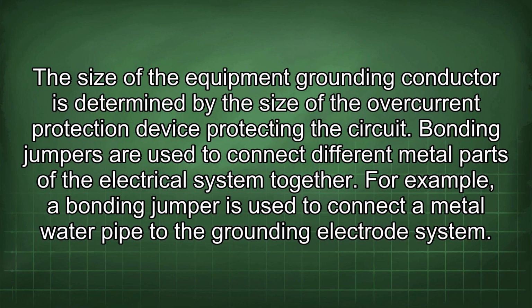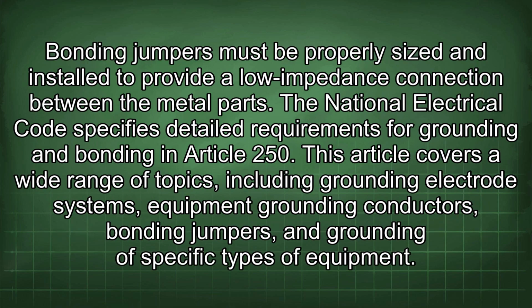Bonding jumpers are used to connect different metal parts of the electrical system together. For example, a bonding jumper is used to connect a metal water pipe to the grounding electrode system. Bonding jumpers must be properly sized and installed to provide a low impedance connection between the metal parts. The National Electrical Code specifies detailed requirements for grounding and bonding in Article 250.